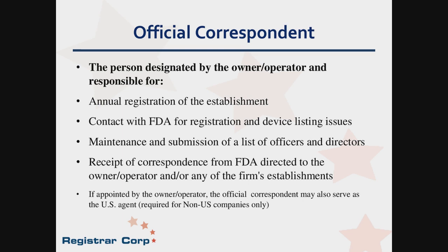The official correspondent is the person designated by the owner-operator and is responsible for the annual registration of the establishment. Also, updates should be done during the year. FDA really requires you to keep the data on the account as current as possible. So if you add new devices that you are manufacturing for the US market, please do updates during the year. Also, you are required to identify your business partners here in the US, or vice versa, your manufacturer, if you're a US importer outside of the US. Please keep this information as current as possible, because we have seen that FDA is detaining shipments because that identification on the accounts is not made correctly.